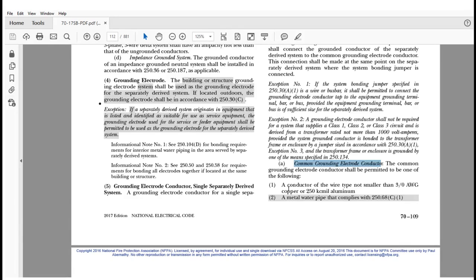and said, look, and metal water piping that complies with 250.68(C)(1) now, which again is an extension or being considered a conductor, as long as it complies with all of the allowances of 250.68(C)(1), was actually added to the allowable methods for a common grounding electrode conductor for multiple separately derived systems. So that's what was added. And the revision also made for the metal structural frame of a building or structure to qualify as a common grounding electrode for multiple separately derived systems. So they spelled it out, itemized it out a little better, and made it clear.